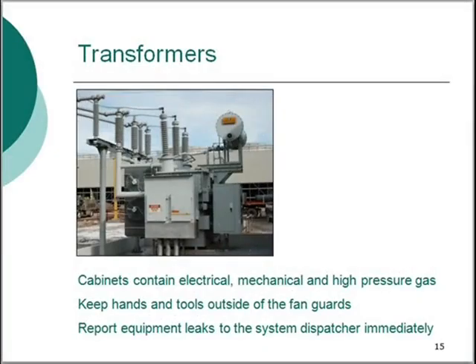Transformers reduce or increase voltage levels. The energized lines connected to the insulators and bushings on top of the transformers should be out of reach to anyone standing on the ground. The casing is connected to the ground grid and safe to touch from an electrical standpoint. Cabinets should only be opened by qualified personnel who understand the electrical, mechanical, and high-pressure gas hazards. The cooling fans are thermostat controlled, turning on and off automatically during warm weather to reduce the oil temperature in the radiator. Keep your hands and tools outside of the fan guards. If you see indications of an oil leak, report it to the system dispatcher immediately.